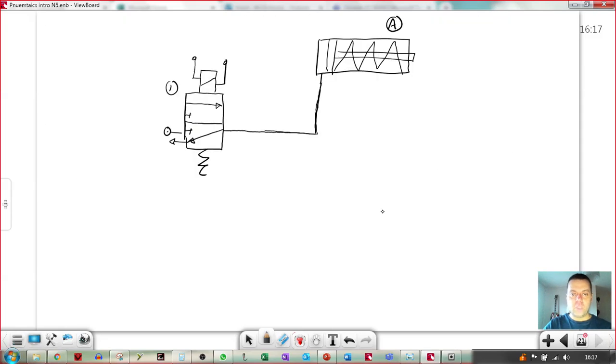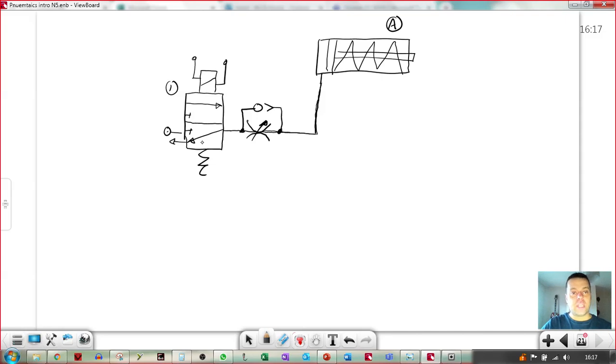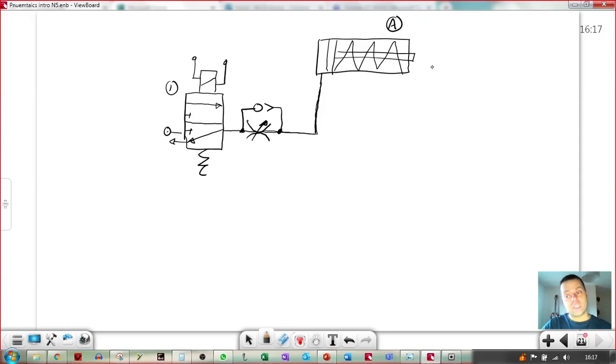So if we just put a flow restrictor there, pointing at the cylinder, then that means that when the solenoid actuates and the main air comes through here, it will take a period of time before this side, the pressure on this side builds enough to move the cylinder.